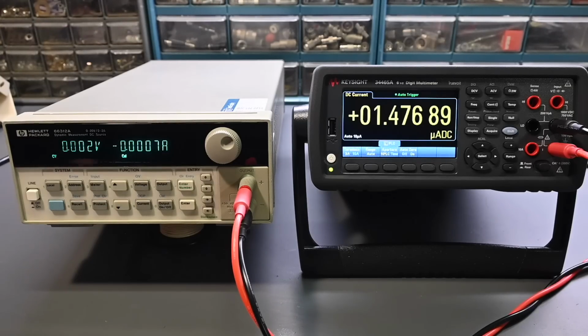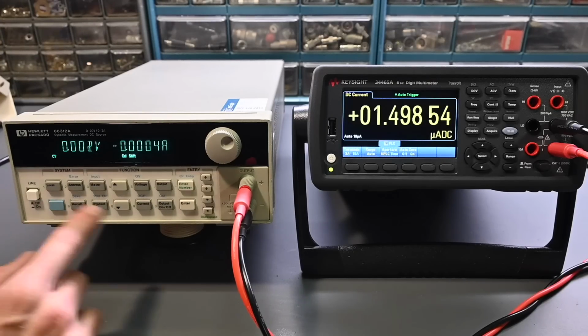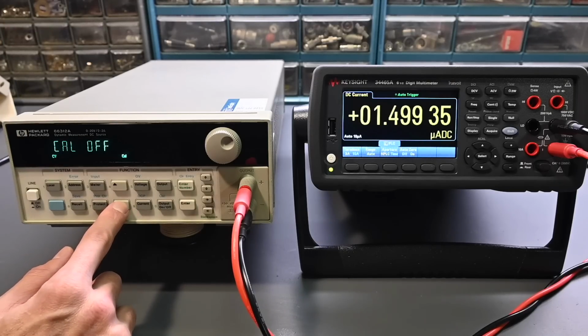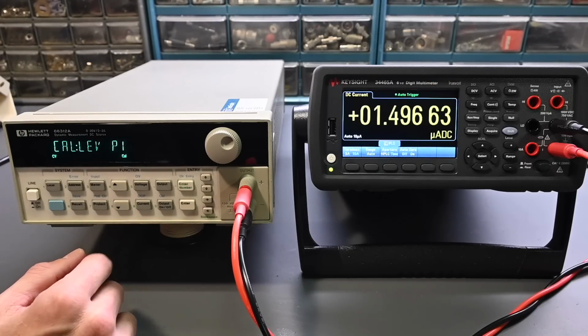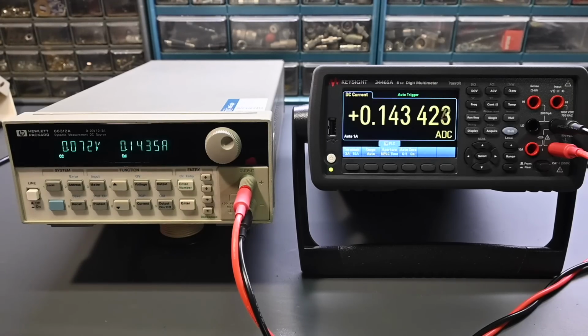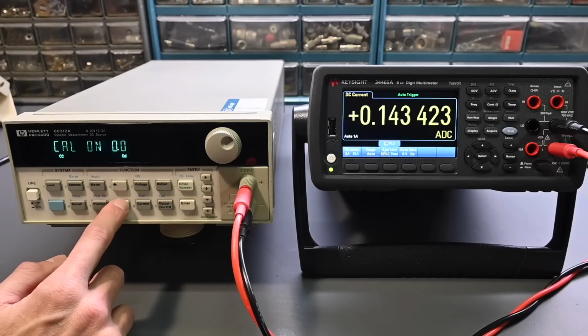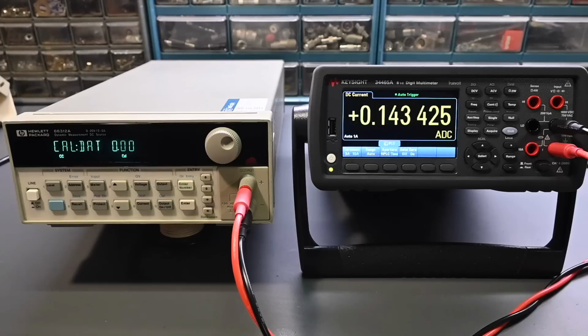Okay, it says to press Shift Cal. Scroll to Cal current. There. Press enter. It says press Shift Cal. Scroll to Cal level. Press enter, and it should be on P1, and it is. Enter. It says press Shift Cal. Scroll to Cal data. It says wait for the digital multimeter reading to stabilize, then read the digital multimeter. They talk about computing the reading divided by the shunt resistance, but we don't need to do that because this has essentially a shunt in it and it's taking that reading for us. So you can read this directly as the current right there.